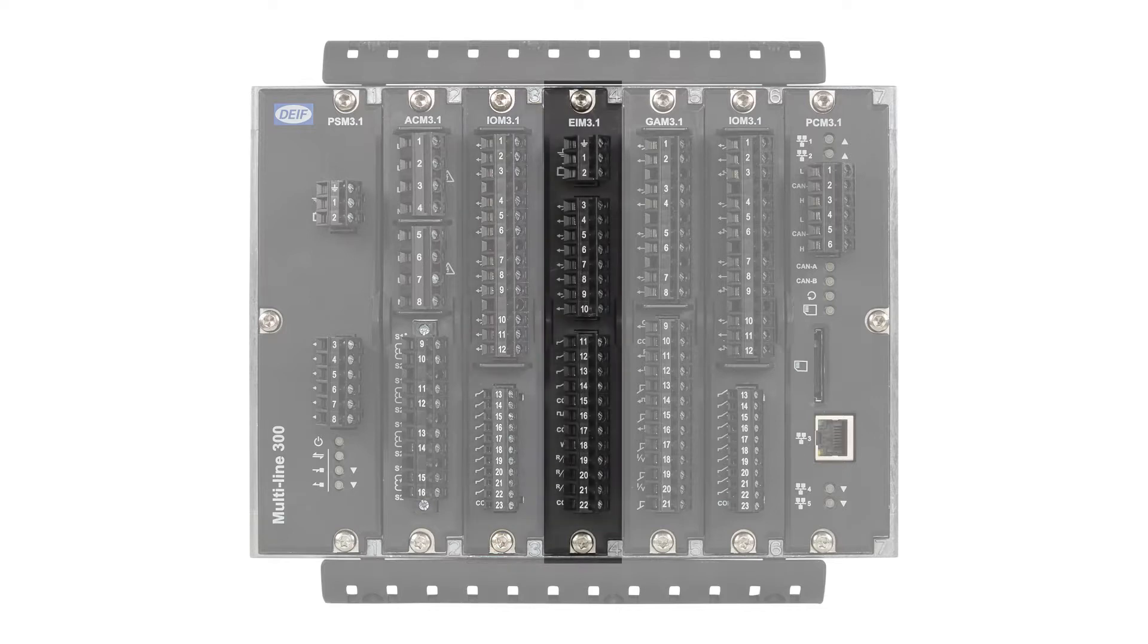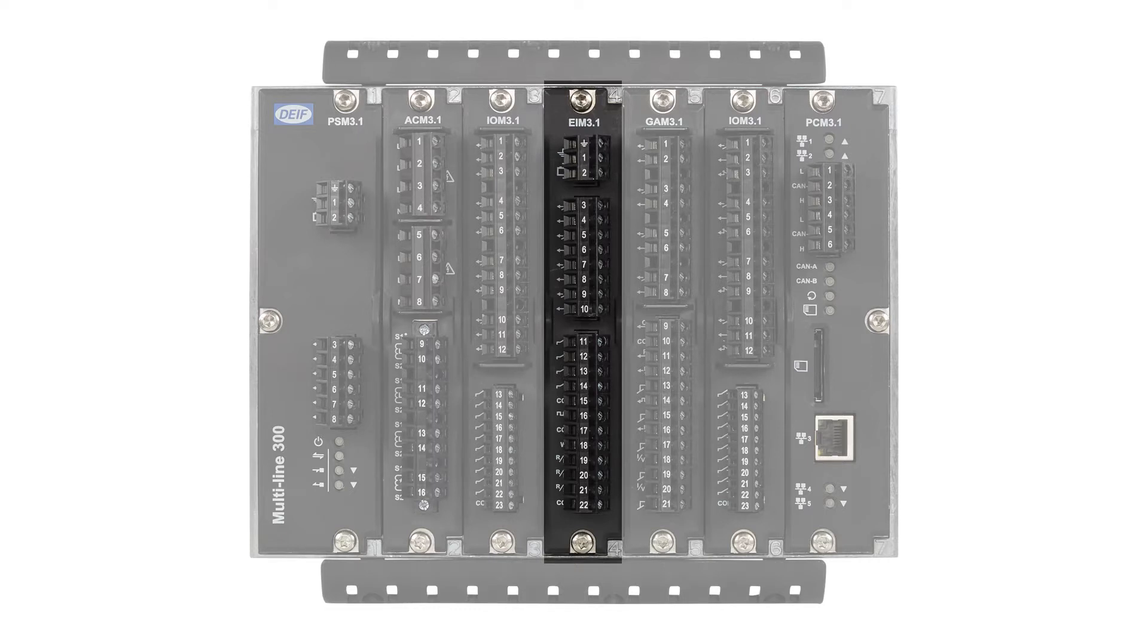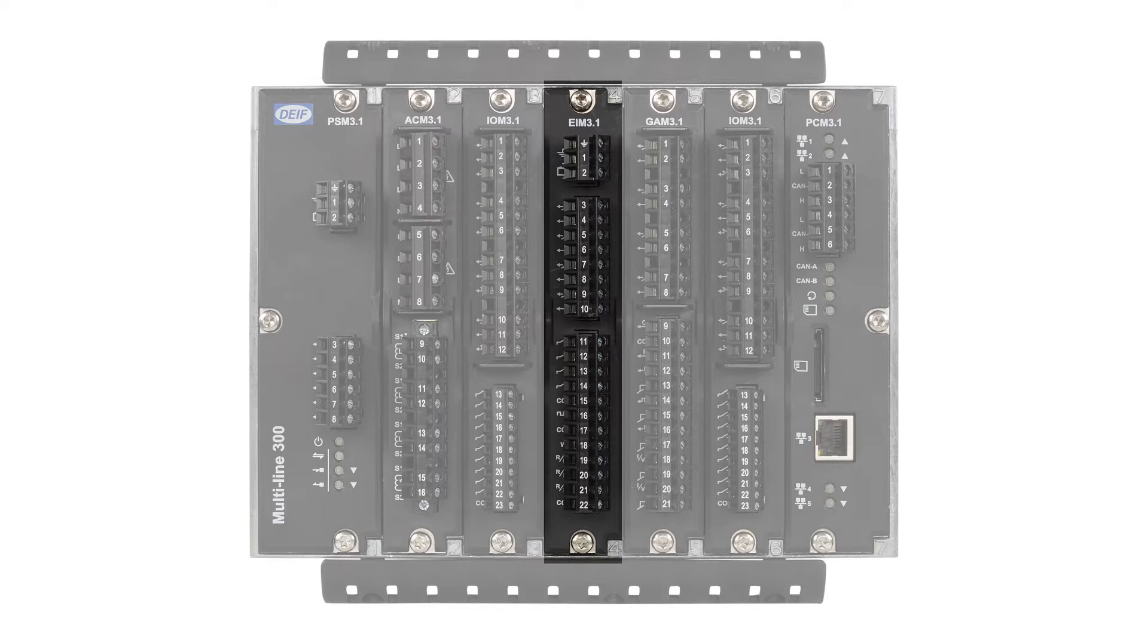The engine interface module EIM 3.1 is installed in the genset and emergency genset controller types. It has its own power supply and an MPU input to measure engine speed. It also has four relay outputs, four digital inputs, and three analog inputs. These are all configurable.